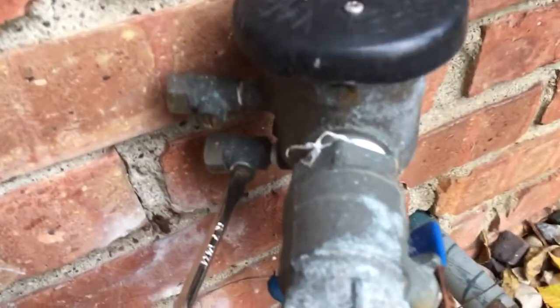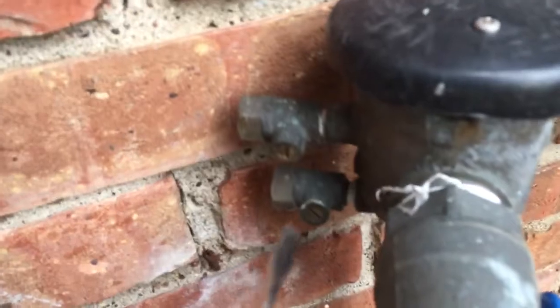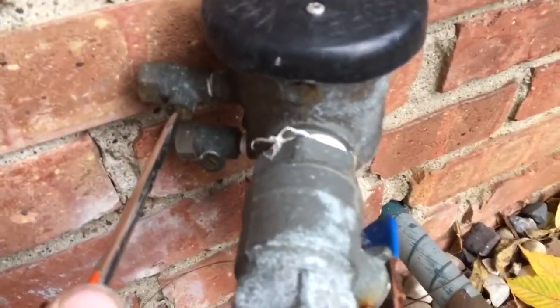See, that'll spit just a little bit. If it doesn't spit and just keeps going, because the pressure in the system will be there — the top one, if it doesn't spit at all, then that check valve will fail. That's guaranteed that it'll need to be rebuilt.